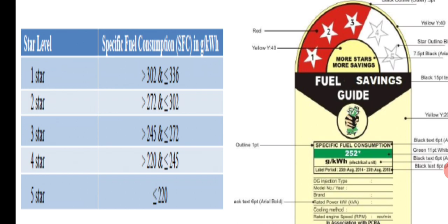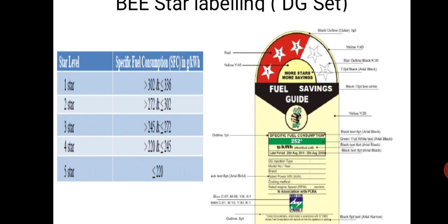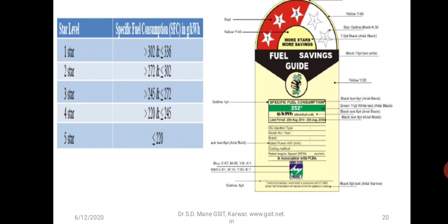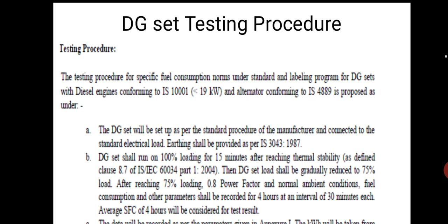Less than 220 grams means that per kg of diesel, they produce almost 4 to 5 units, whereas this one produces only 3 units. So as a layman's thumb rule, 3 units of power per liter versus 5 units of power per liter makes a big difference. The electricity produced by DG sets costs somewhere around 18 to 20 rupees per unit. This is a small procedure that I have shown. I think you can go through this, how the DG sets are tested.